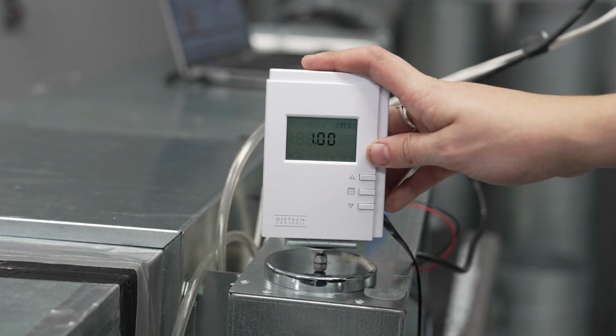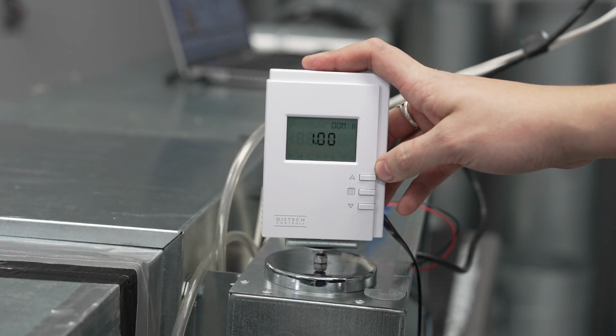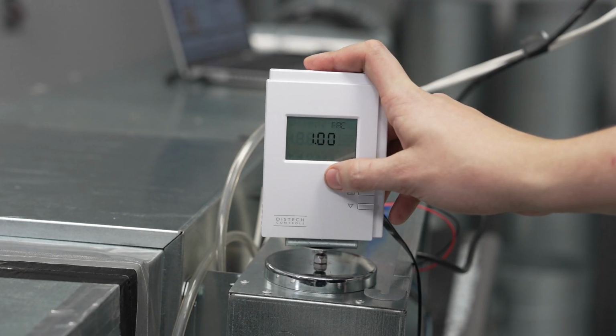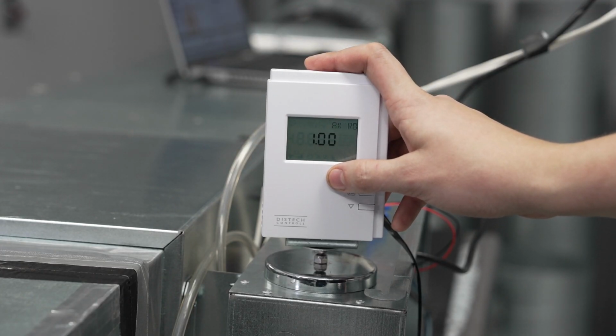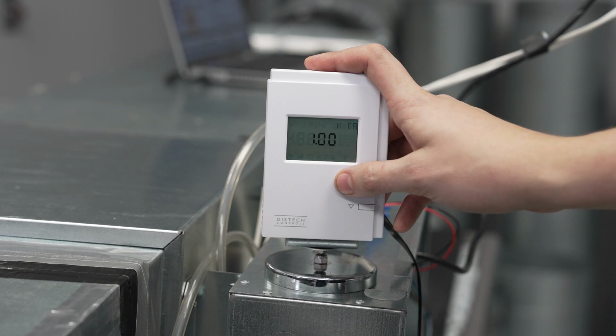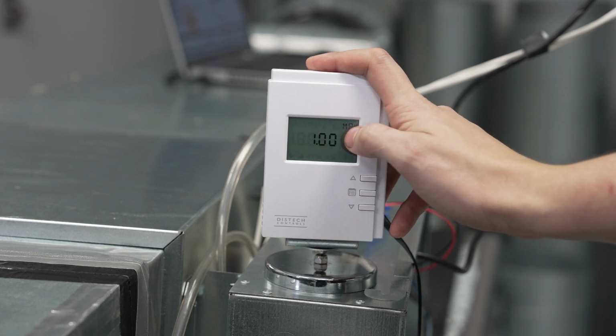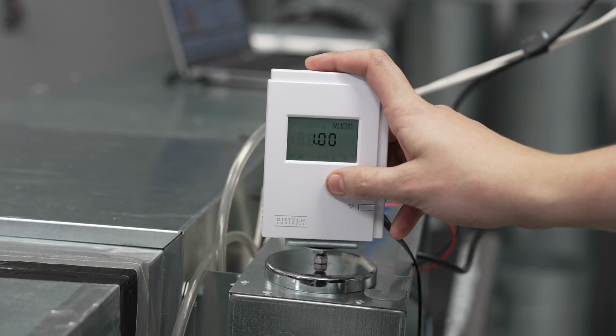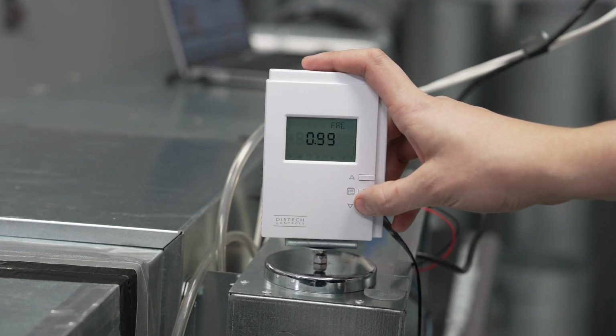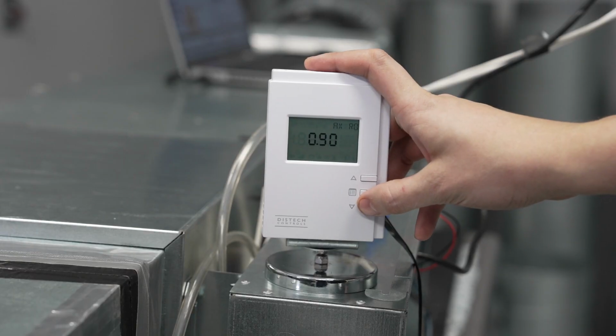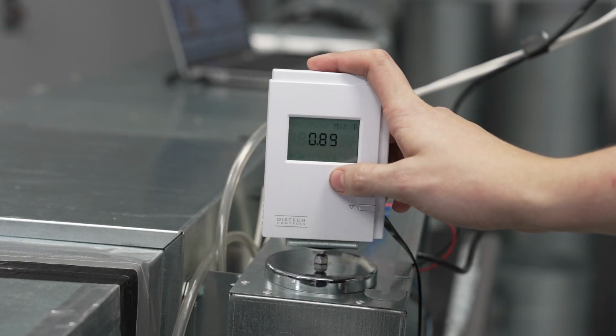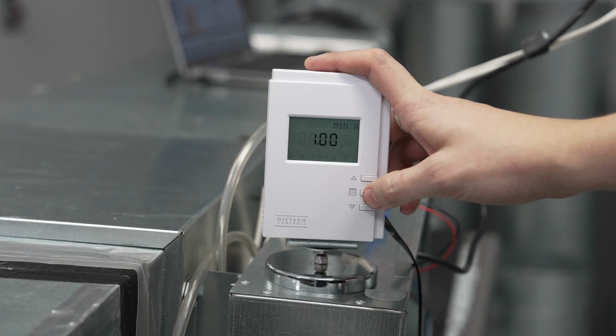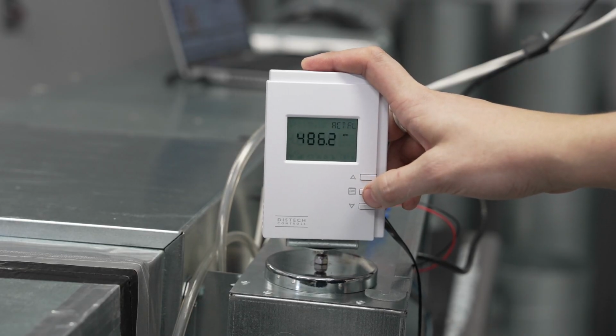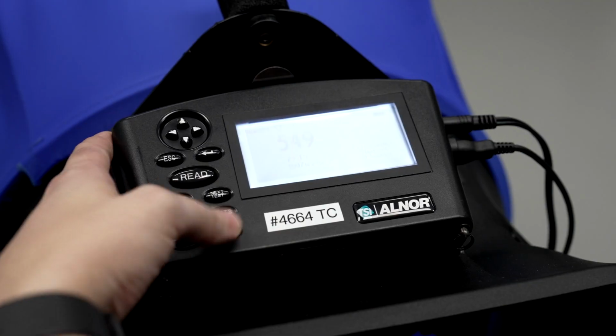HVAC Manufacturing and Technology sent 2 SAVs for third-party testing with our proprietary 2-point K factor adjustment. The 12-inch round SAV was shipped with the normal calibration equation derived from a calibrated airflow chamber. The 10-inch high by 15-inch wide low-profile rectangular SAV calibration curve was offset by 11% to simulate system effects due to inefficient duct installation and design. The 11% error was properly measured by both the calibrated flow stand and duct traverse. The capture flow hood was off by 9%.